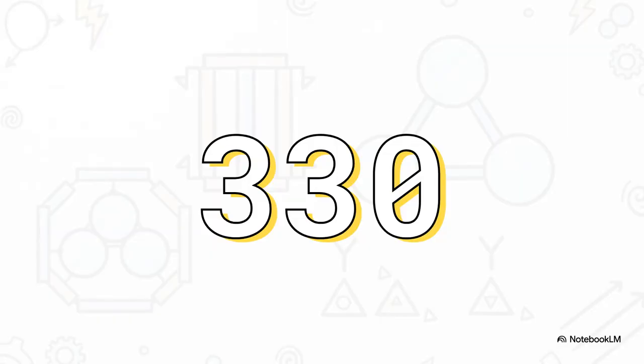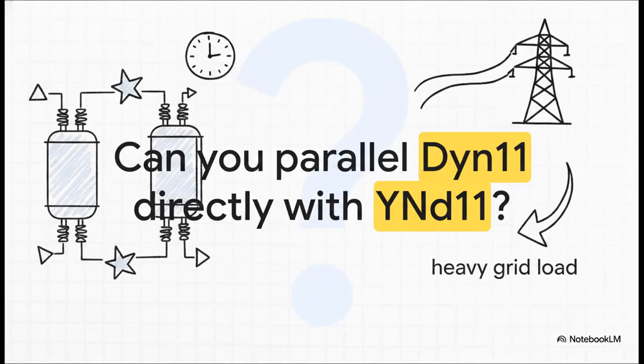That 11 isn't just decoration, it's actually a clock position. When you multiply that clock position by 30 degrees, it tells you exactly the phase relationship between your primary and secondary voltages. So 11 times 30 means the secondary voltage lags the primary voltage by exactly 330 degrees. Pretty cool, right? So let's try a high-stakes application question. If two different transformers both use delta and star windings, can you safely parallel a Dyn11 transformer directly with a YNd11 transformer to share a heavy grid load? Just take a quick second to think about what we literally just learned regarding those clock numbers.